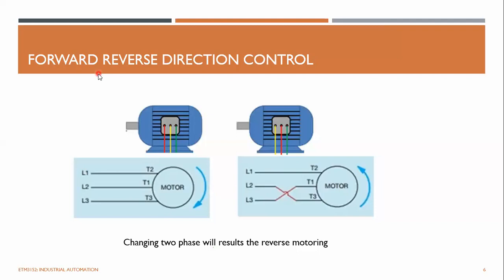All right, so now we can take a look at the forward and reversing of an induction motor. This might be very familiar to you if you have learned this in electrical machines. In a three-phase motor, you have the motor windings, L1 and T1, T2, and T3, or W, U, V, different notations. If you want to run it in one direction, this is the wiring. If you want to change the rotation direction, you can swap two wires. The magnetic field will change direction, and the motor rotation will change.